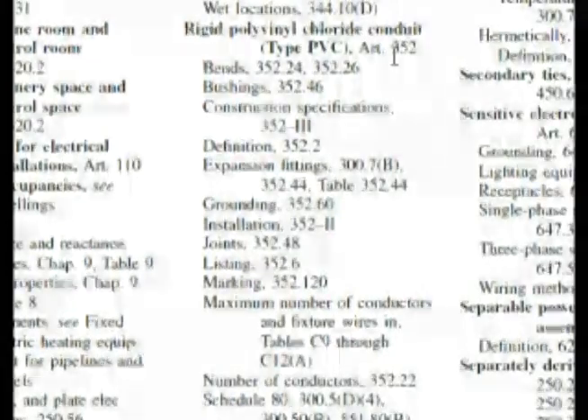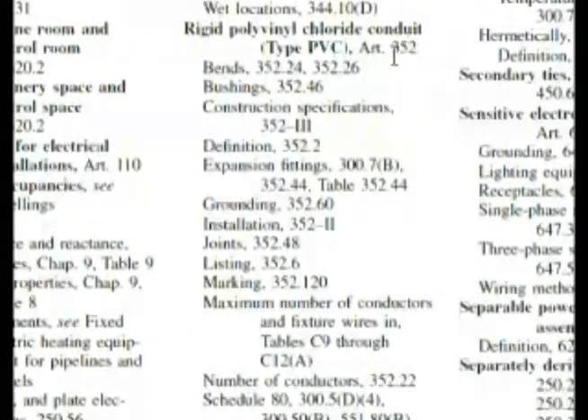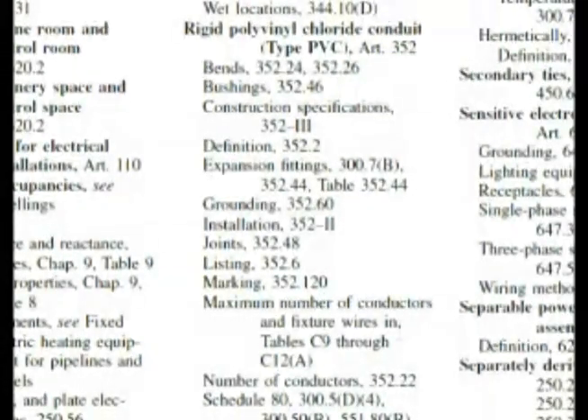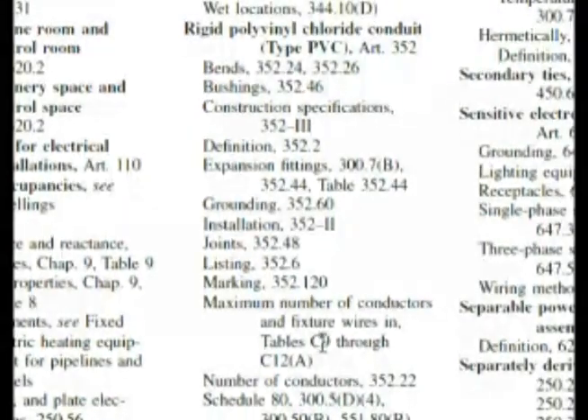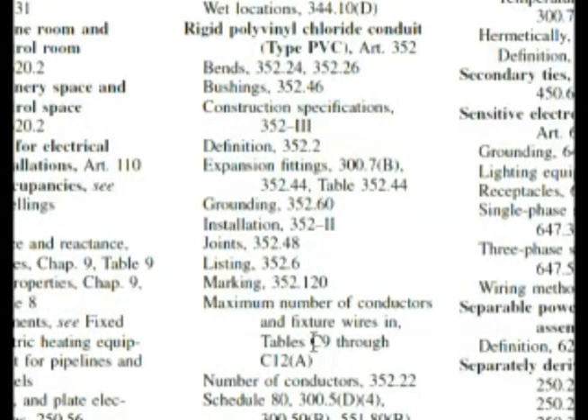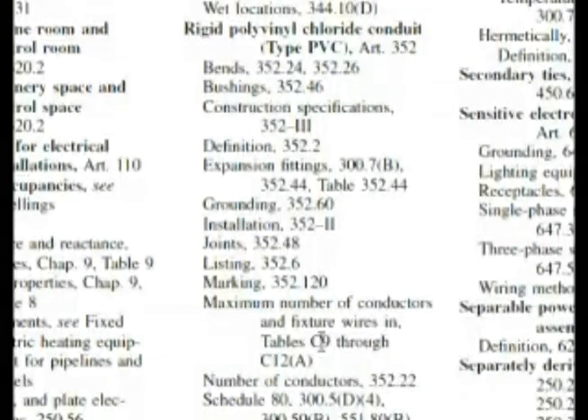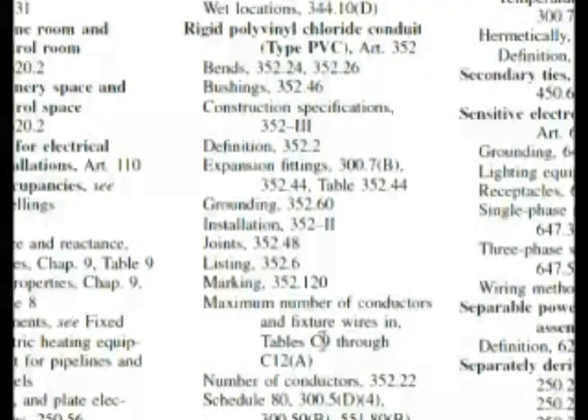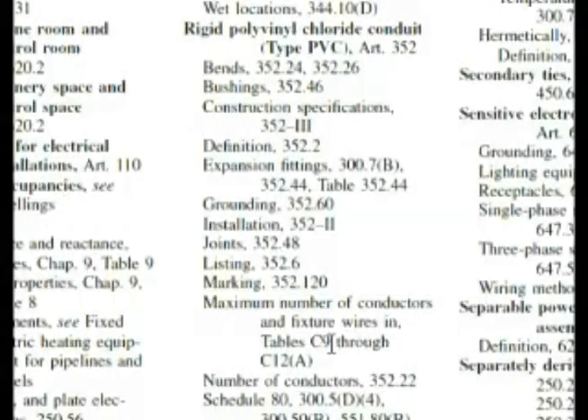Here we are in the index — you can see rigid polyvinyl chloride conduit, listed as PVC, leaving the R out for some reason. It's article 352, which comes past Table 310.16, one of our answer choices. We have maximum number of conductors and fixture wires in tables C9 through C12A. This is actually Annex C, and Annex C9 through C12A deals a lot with wire fills for PVC.